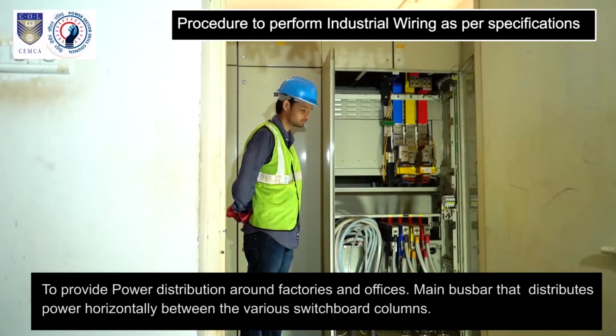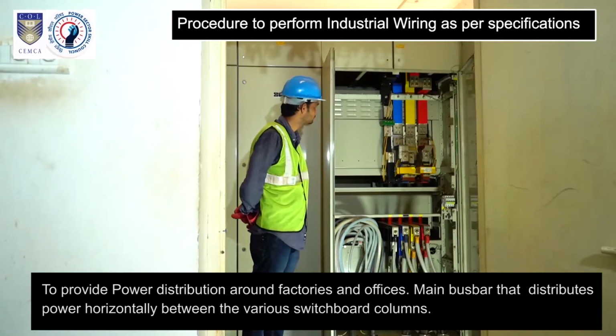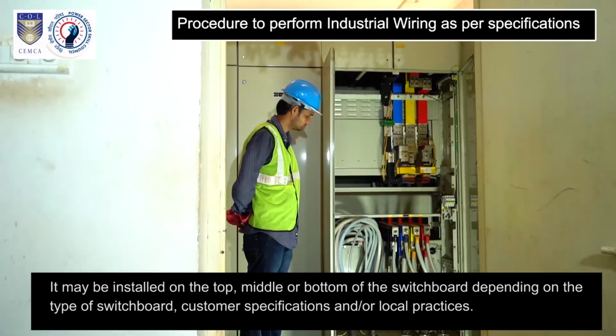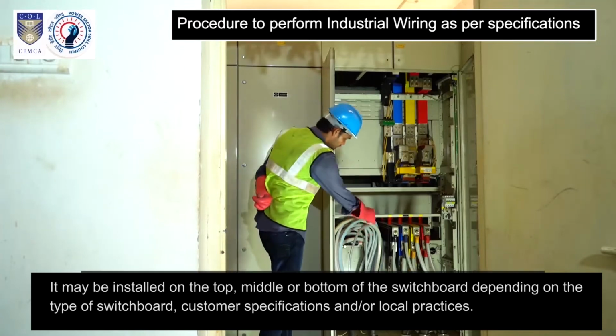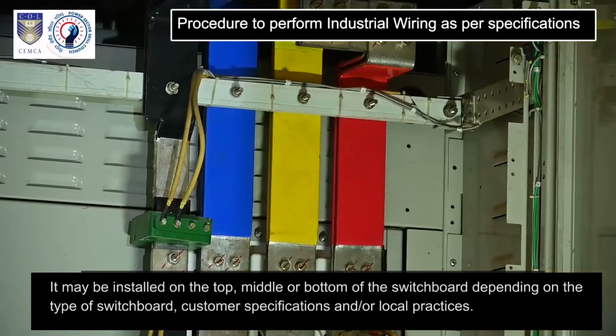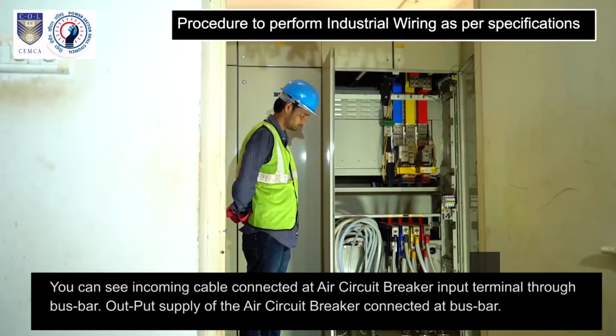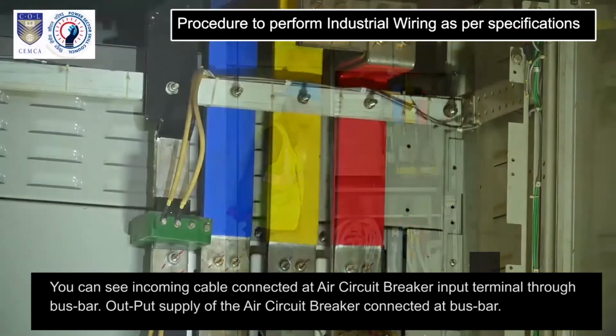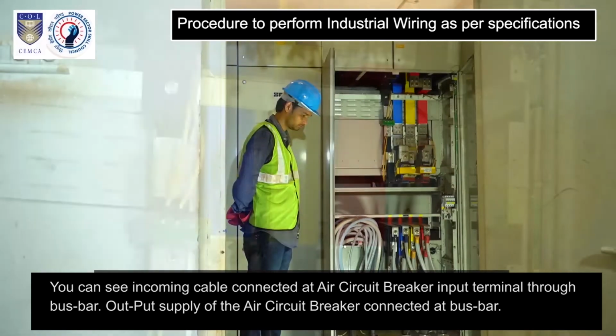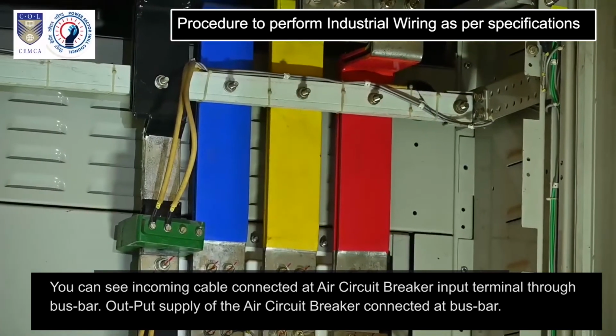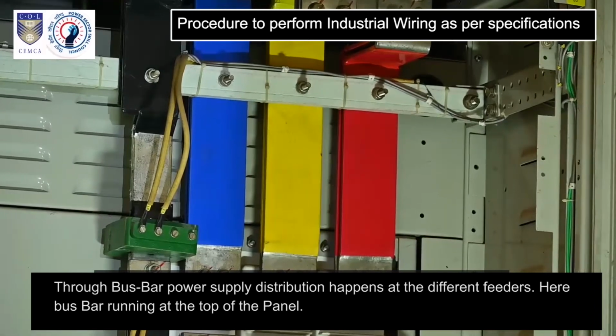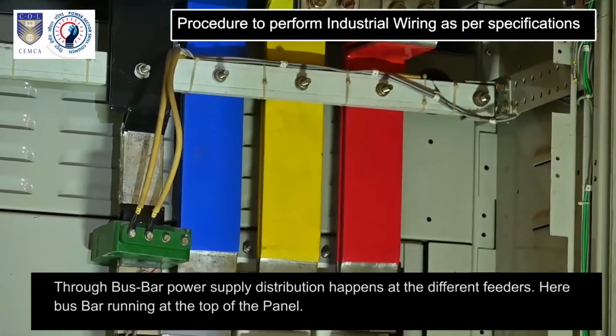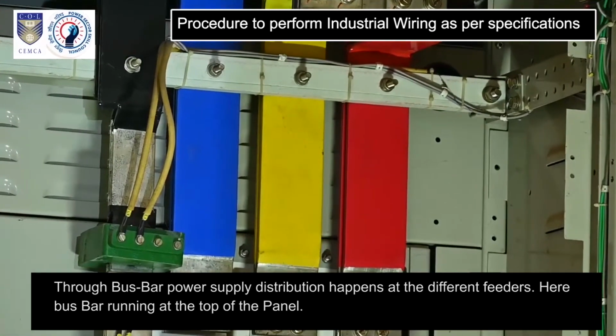Main busbar that distributes power horizontally between the various switchboard columns. It may be installed on the top, middle or bottom of the switchboard depending on the type of switchboard, customer specifications and/or local practices. You can see incoming cable connected at air circuit breaker input terminal through busbar. Output supply of the air circuit breaker connected at busbar. Through busbar power supply distribution happens at the different feeders. Here busbar running at the top of the panel.